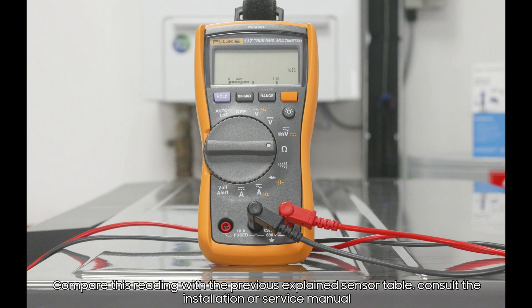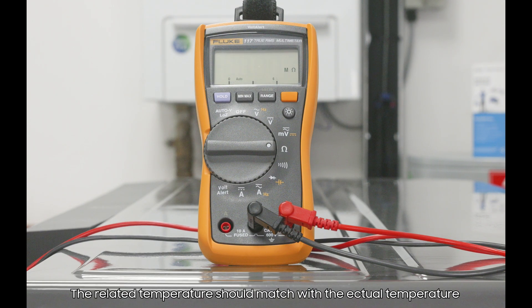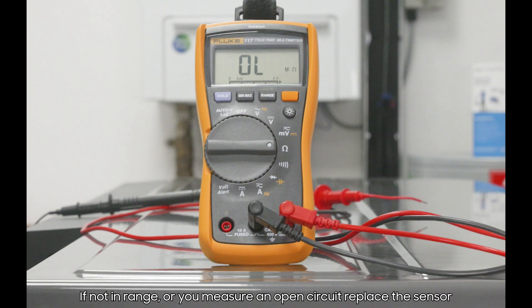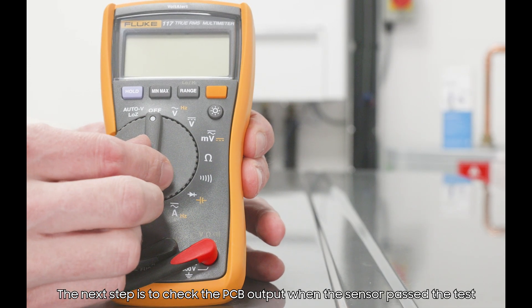Compare this reading with the previously explained sensor table. The related temperature should match with the actual temperature. If not in range or you measure an open circuit, replace the sensor.